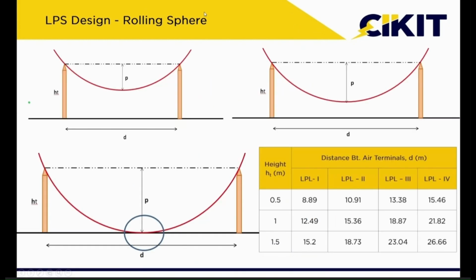So if I increase this distance between two air terminals, more portion of the sphere will be coming below. And if I increase further, then more portion will be coming below. And if I increase more, then the sphere will be making contact with the structure to be protected. If the sphere is making contact with the structure, then that particular portion will become unprotected.